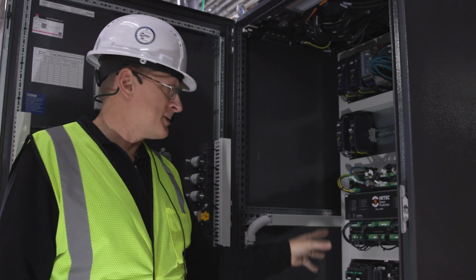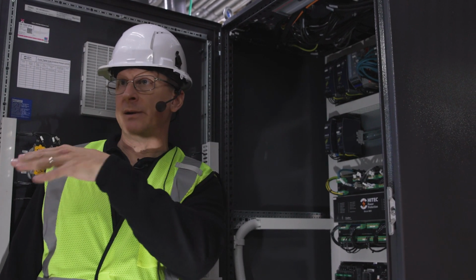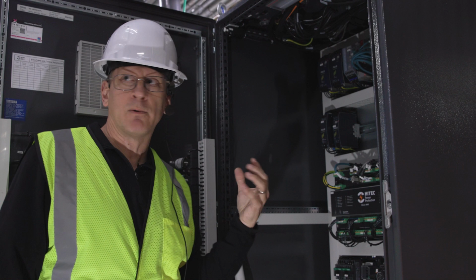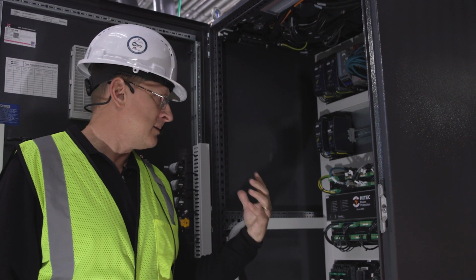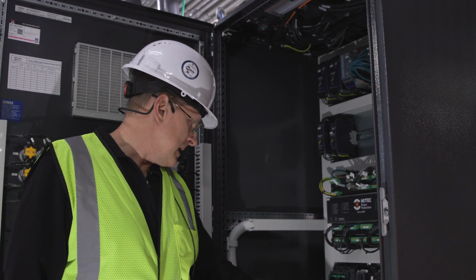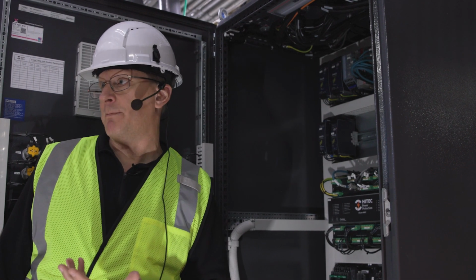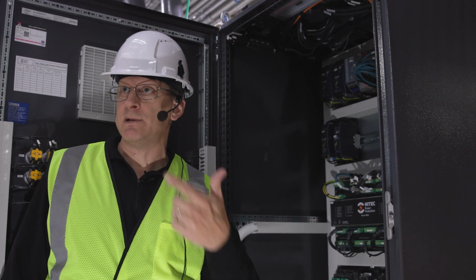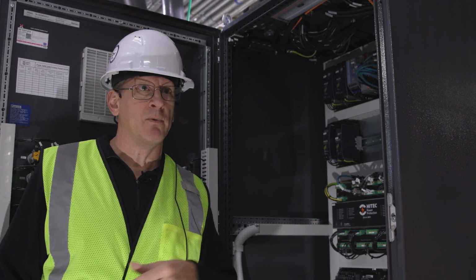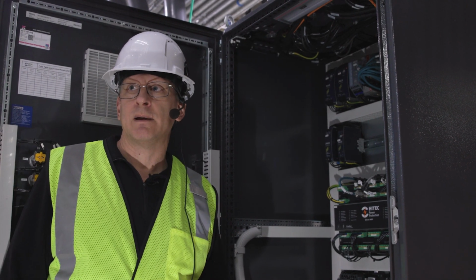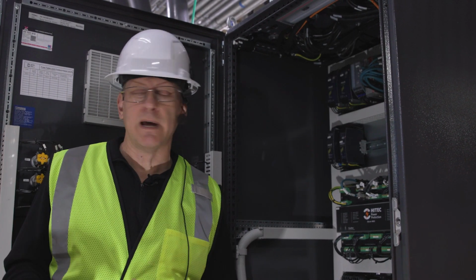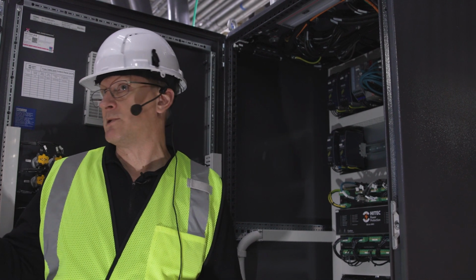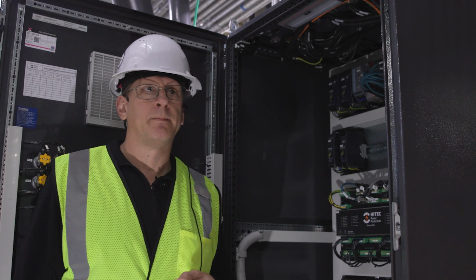This unit, this PLC, communicates with all the other panels through an IP network. So each panel and each device that is linked to the PLC has its own specific IP address. That's how it communicates. There's Cat6 cables that run from panel to panel that basically establish the network so that this unit can communicate with the switchgear and the other panels.